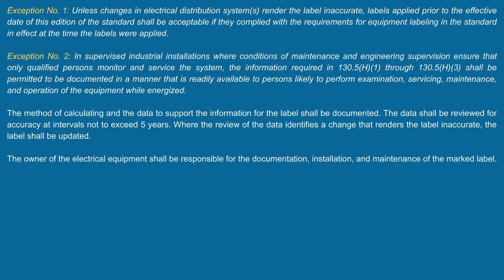Now, they have some exceptions here that they look at, and exception 1 says, unless changes in the electrical distribution system or systems render the label inaccurate, labels applied prior to the effective date of this edition of the standard shall be acceptable if they complied with the requirements for equipment labeling in the standard in effect at the time the labels were applied. So they're going to allow those labels to stay on there. But the way I look at this, that becomes a problem, especially after 5 years, because you need to go in and look at it anyway. And if it has changed, now you need to bring that labeling up to whatever the new changes are.